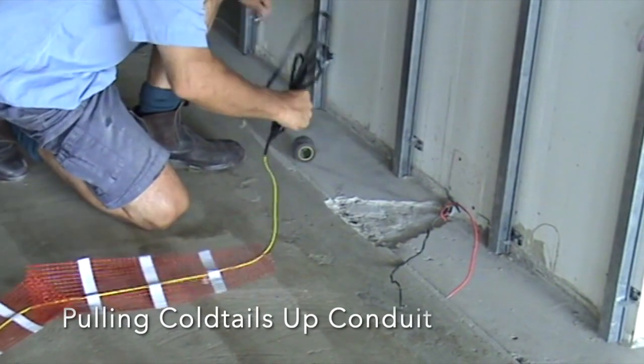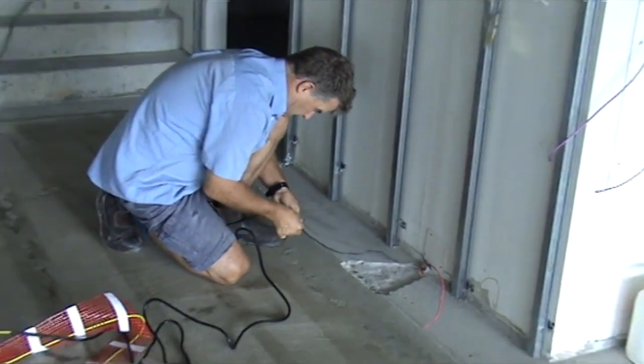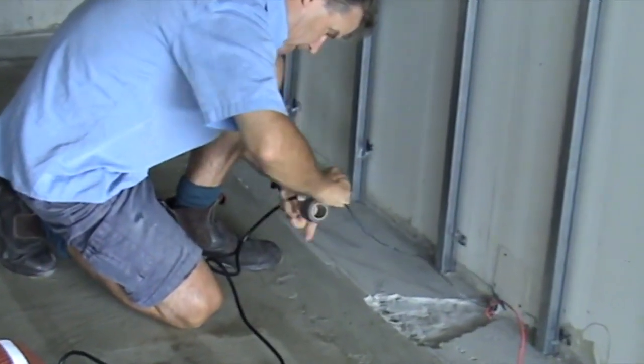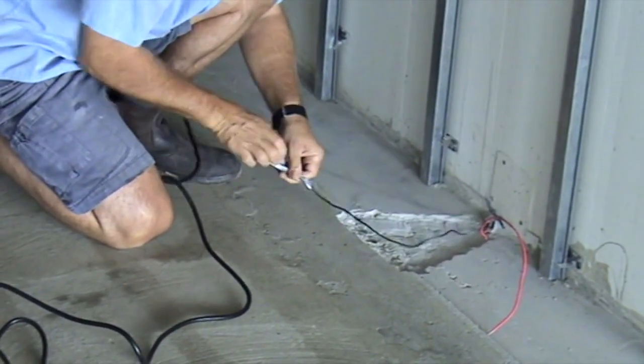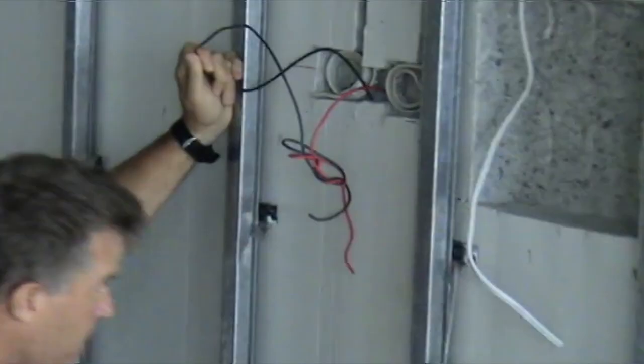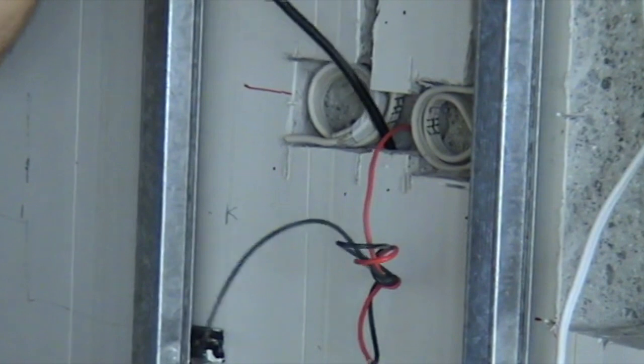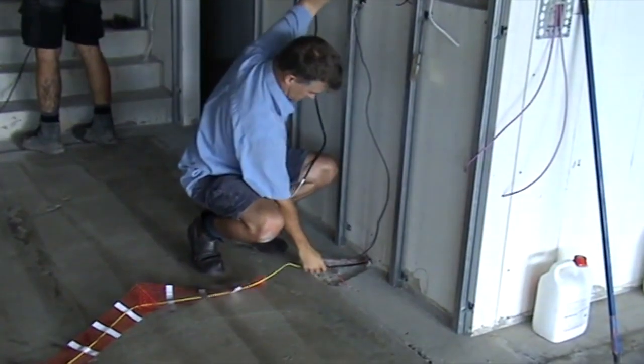First up, attaching your coldtails to the draw wire — take them on one at a time per conduit, make sure it's well connected, and then pull the draw wire up the conduit feeding in the coldtail at the bottom until you've pulled the full coldtail out and the junction is sitting at the recess in the floor.